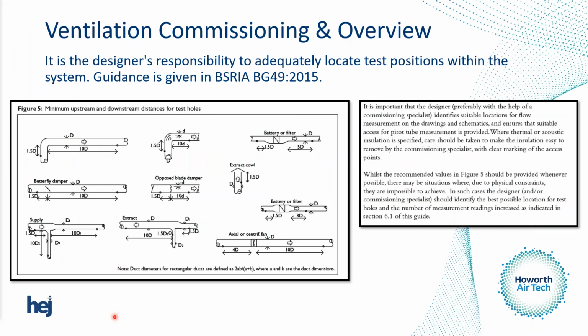So keeping in line with the ventilation design then, this is an extract from BG49. And for those of us on the call that may be familiar with measuring a velocity within a duct, there's a requirement that those test positions, when we drill into the ducts and put our pitot traverse in so we can use a micromanometer and measure the velocity, must be 10 times the diameter of the duct off the bend. So you can see in this instance 10 times the diameter of the duct to put an adequate test position to enable the air to become more laminar so we can get a reading on it.